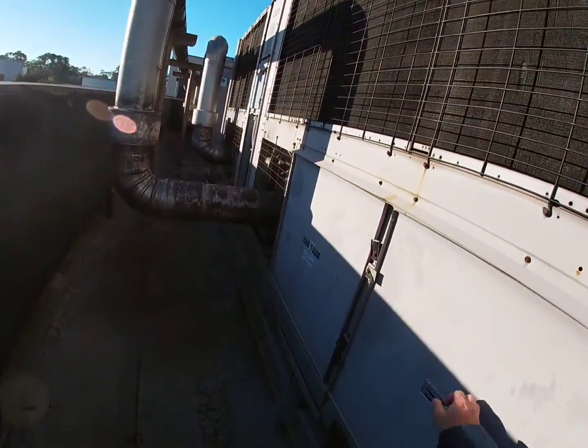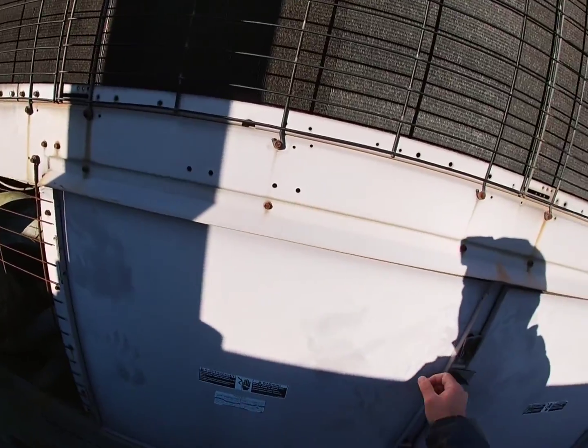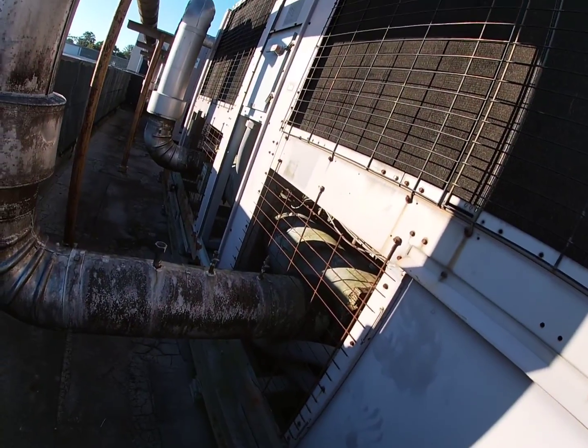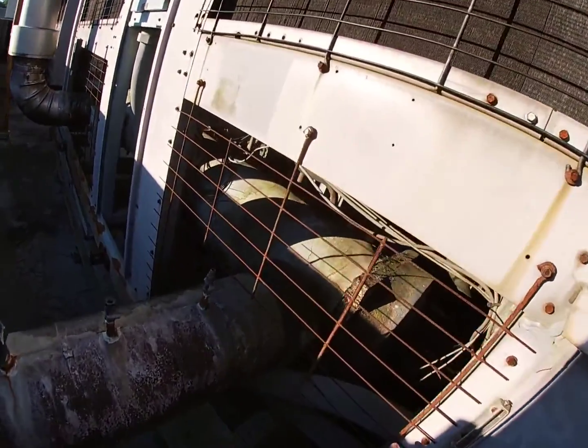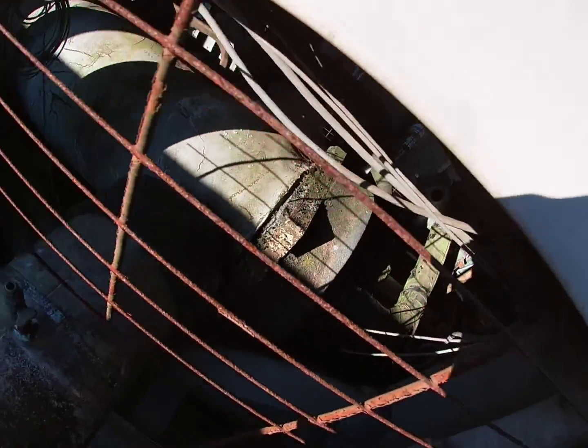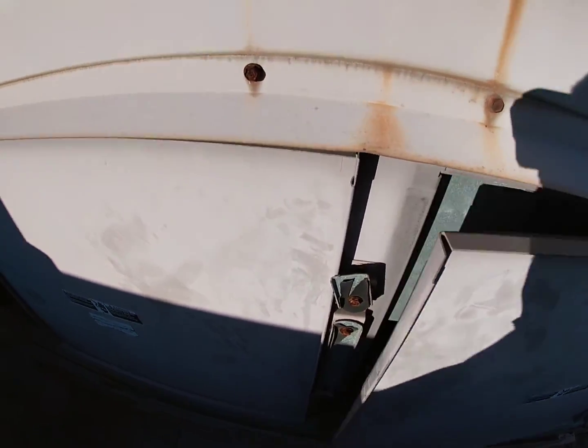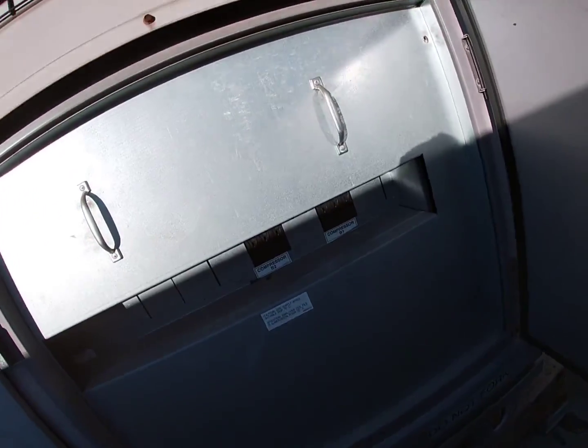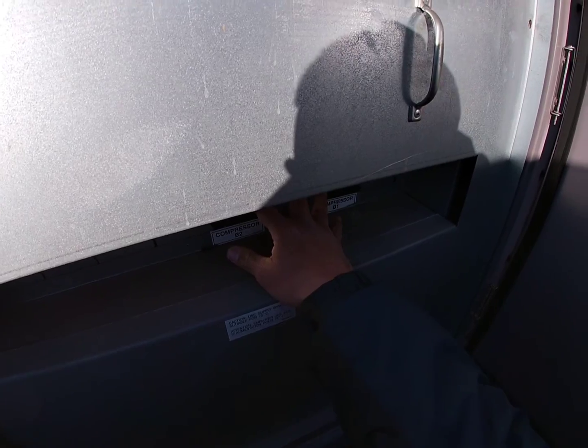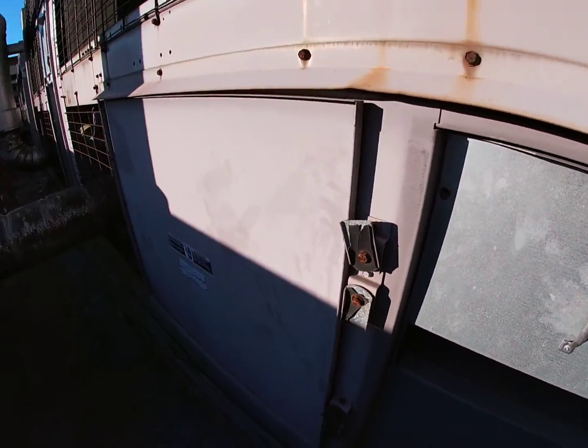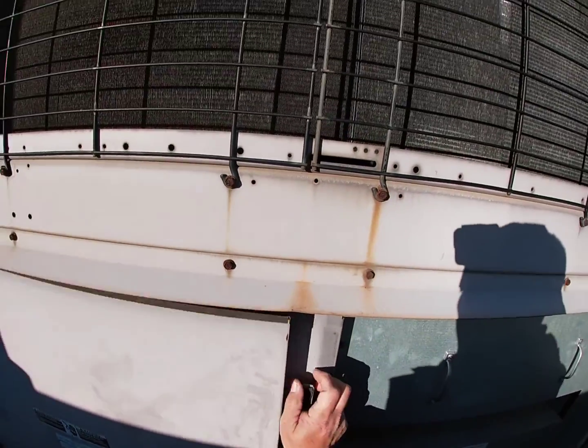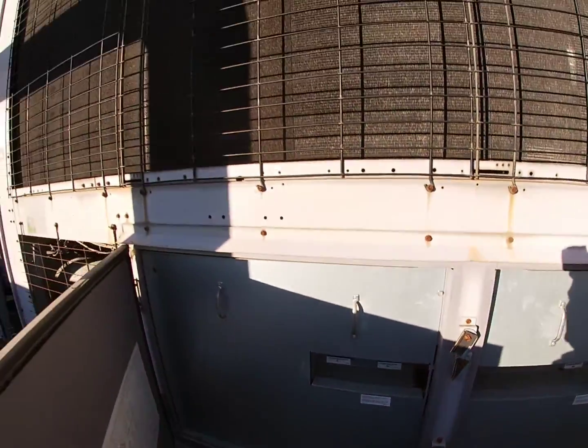and then over here you have your breakers for your compressors. And then over here you have your EXVs. So let's see. So in there you got your breakers. They do have these two off. They were having issues with these two compressors. I think they had one compressor was grounded, so they got both of those off on that circuit there. Both of those, all three of those are on. So, yeah.